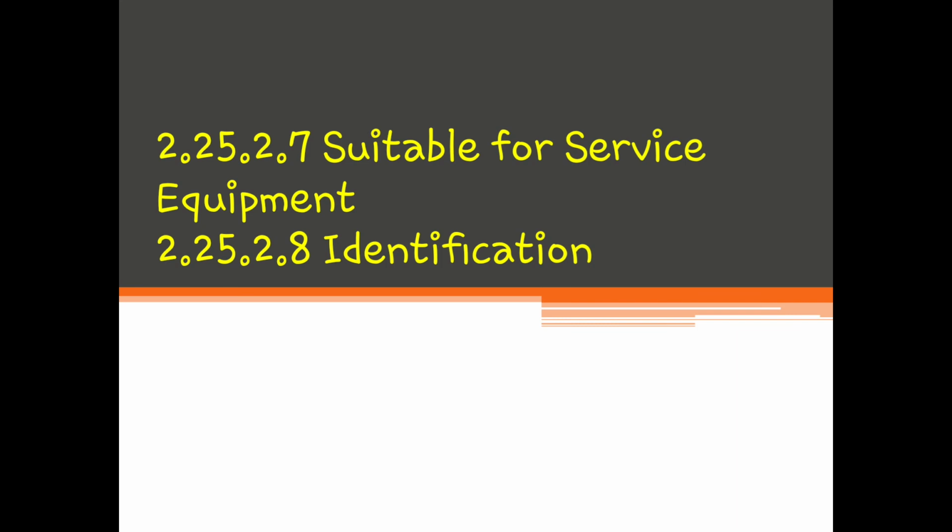Once gali ang building or a structure kay naay combination of feeders, meaning na one or more feeders iya ang supply sa iya, then there's a need to have a permanent plaque or directory to be installed at each feeder and branch circuit disconnect location denoting all the services, feeders or branch circuit supplying that building. So need siya og plaque or directory.